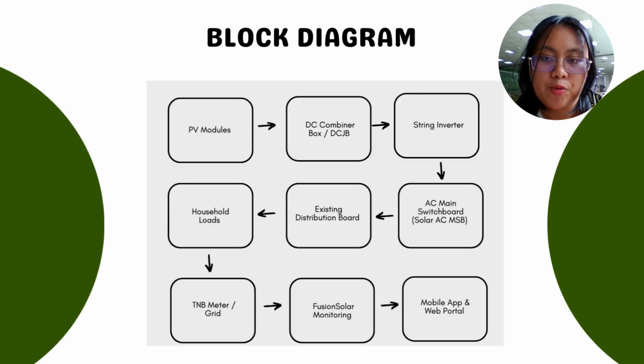Our block diagram is as follows: the PV modules will supply the energy to the DC combiner box, DCJB, and after that DCJB will send the energy to the string inverter, and the string inverter will transfer the power to the AC main switchboard, MSB. The MSB will transfer the power to the existing distribution board, and this board will supply the energy to the household load. Then the meter we use in our Fusion Solar monitoring. We can monitor this using the mobile app or the website.